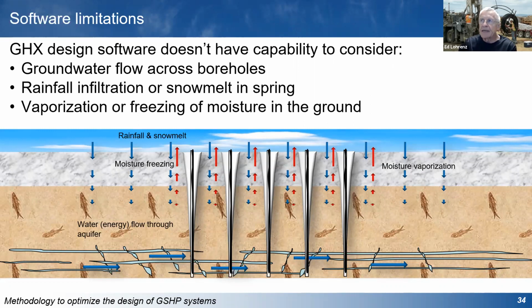If you're drilling, for example, in a place that's primarily shale, even if there's moisture in the ground, moisture doesn't move very well through clay and shale. So you're not going to get the impact of water flow across the borehole field or infiltration very much. And in that kind of situation, the software might predict the temperatures more accurately than it would if you were in a sand and gravel aquifer where there is a lot of groundwater movement or infiltration.